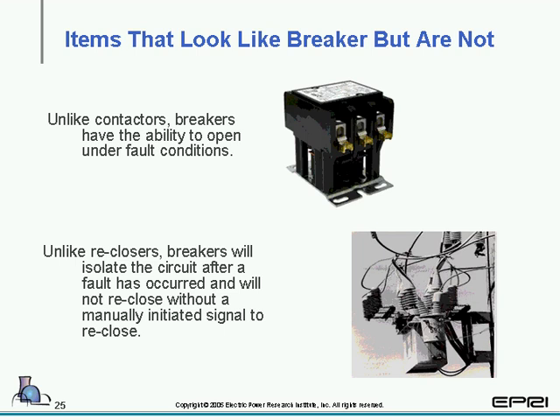And unlike reclosers, breakers will isolate the circuit after a fault has occurred and will not reclose without a manually initiated signal to reclose. Reclosers will close back in under a known fault on the line, and sometimes more than once, after opening from a fault automatically.